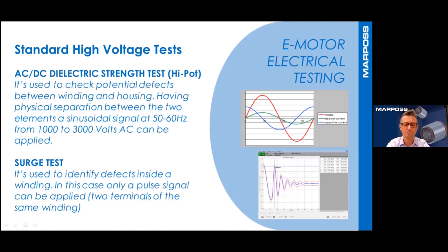Having physical separation between the two elements, a high voltage sinusoidal signal at 50-60 Hz can be applied. The Hi-Pot test can also be carried out applying a DC voltage. The surge test is used to identify defects inside a winding. For example, in case of round shape wire, it may be stressed by the winding machine if its speed is too high. In this case, having two terminals of the same winding, only a pulse voltage signal can be applied.